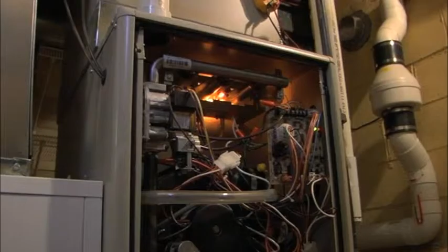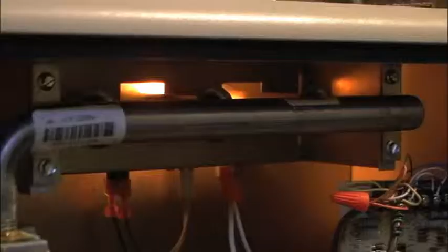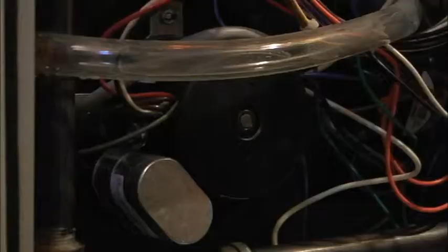Once the furnace is back and running, they will fire the furnace, inspect the flames, make sure that older furnaces are drafting properly so that you don't get carbon monoxide spilling into the house. A lot of these furnaces have various safeties, such as flame sensors to prove a flame is on. They'll have limits to check for overheat, pressure switch to make sure that the flue isn't plugged. All these safeties are checked to make sure that they are doing what they need to do to protect you.